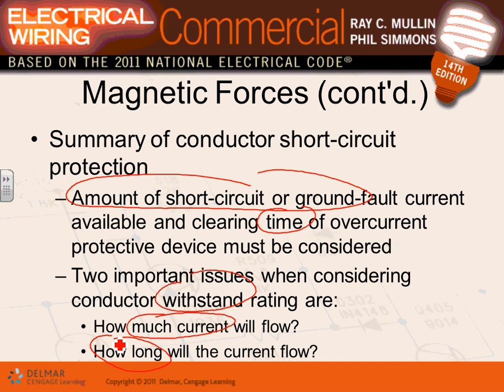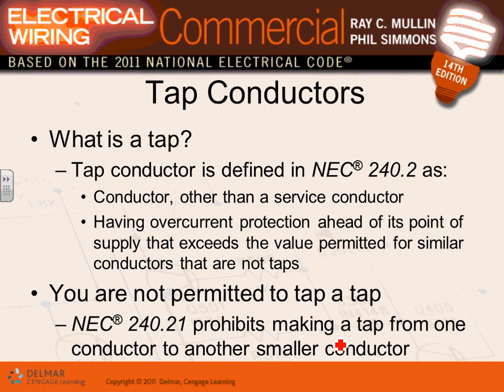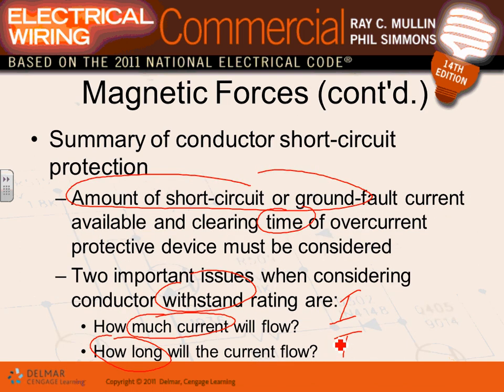Like everything else, guys, I can put pressure on you. If I want to pressure your hand, wrestling, or look at the games, any game, right? It's not just about how much. Now, how long is more important, because how long will emphasize the energy. How long, time, I can't emphasize enough. The current as well as the time is a major part of the arc flash condition. Okay. Any comments, guys? Any questions? That's basically the withstand rating for equipment and conductors.